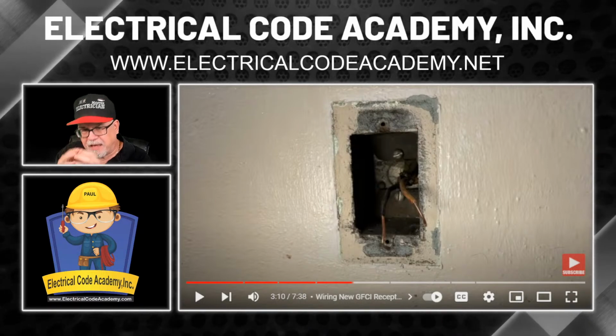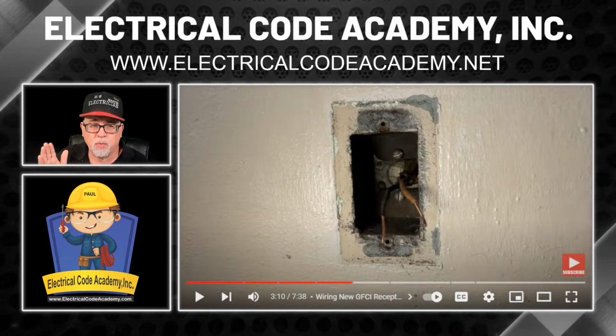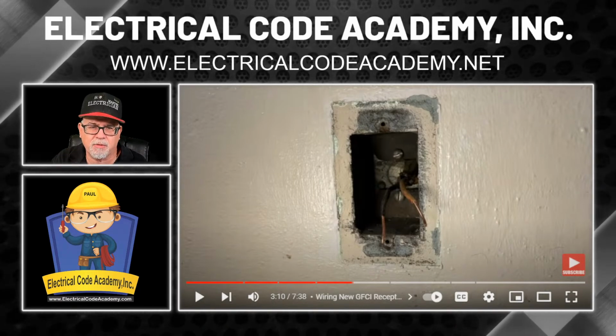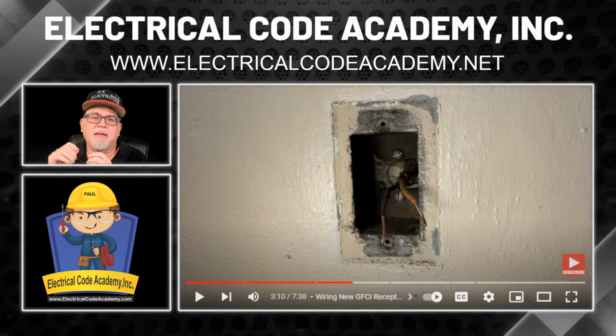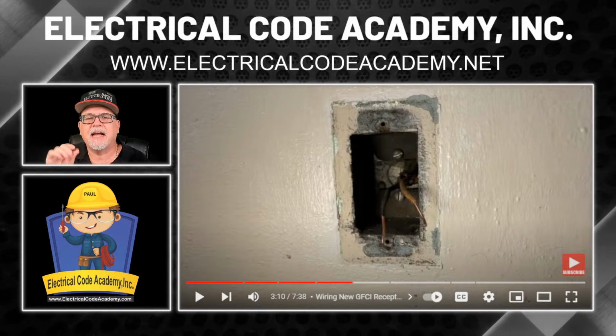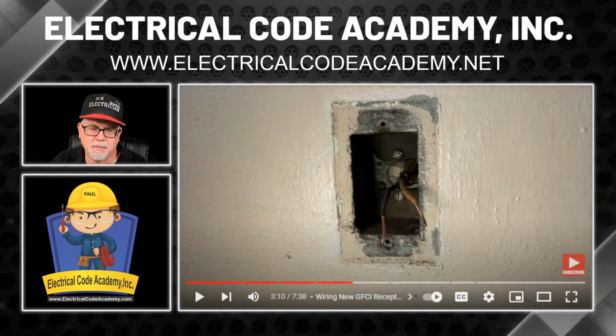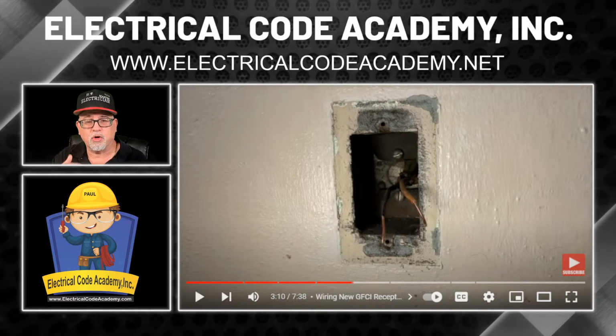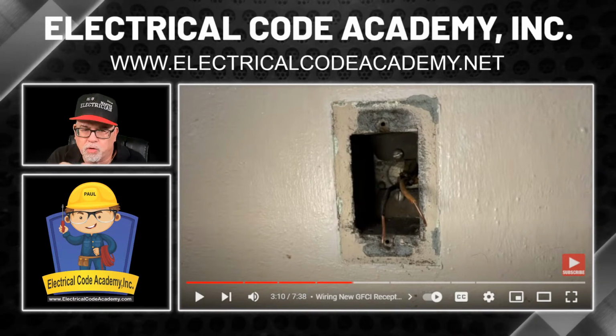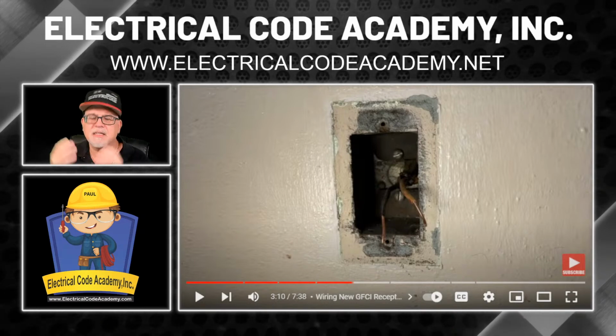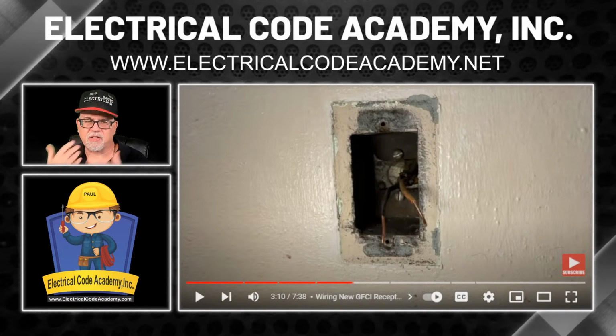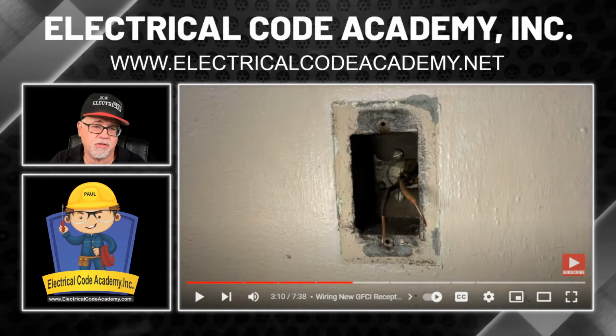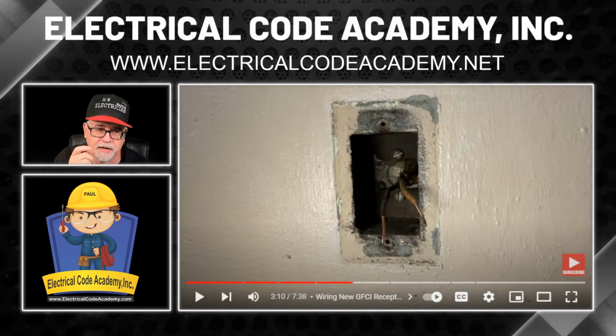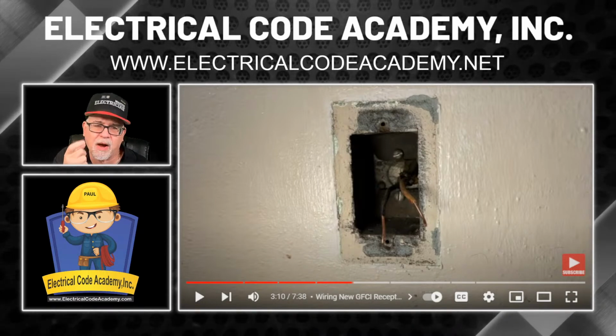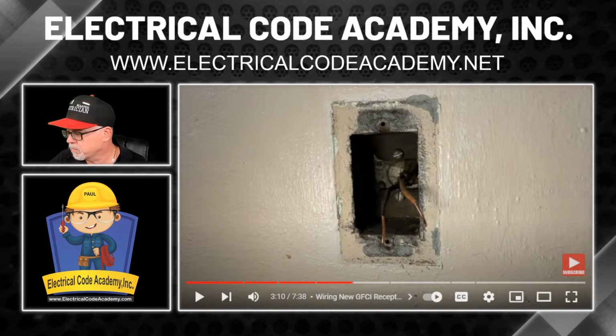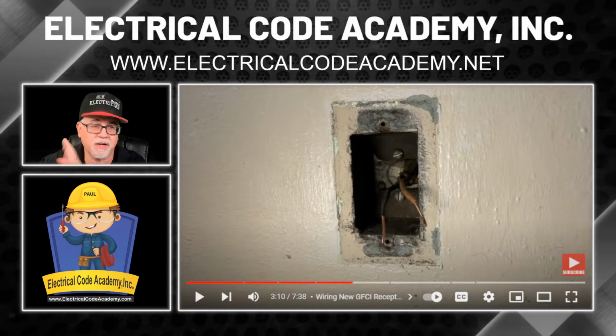So I would splice on my pigtails of the fresh new wire. Maybe I stripped it out of some non-metallic sheath cable or what have you. And then I wire nut them on here to extend them. And then I tuck and fold those nice and neatly back in the back of the box. Now I've got enough free conductor to work with my device. I don't have to work real close to the wall. I can do everything nice, and again, it just makes it much easier to work. Again, you do you, I'm just giving you some commentary. I do not like working with little teeny pieces of wire sticking out of the box. That's just me. Okay, just wanted to get that out of the way.